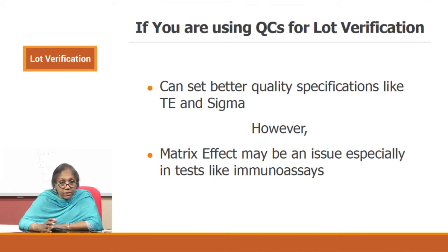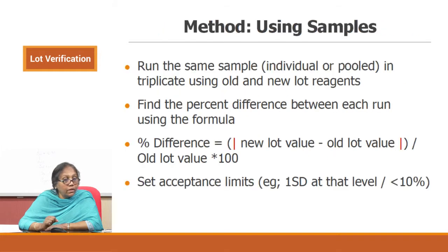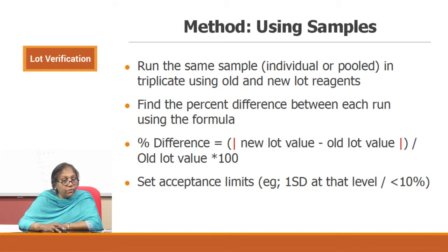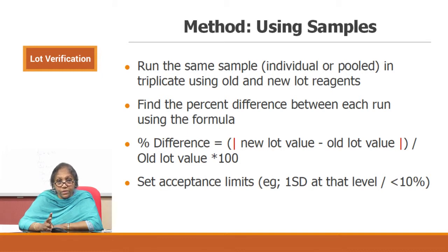Both methods are advisable — it is your choice. For the sample method, you may need to pool samples because if you are going to run the same sample with the new lot and the old lot in triplicate, that calls for 6 runs consecutively. So it can be done using individual or pooled samples in triplicate using the old and new lots of reagents.